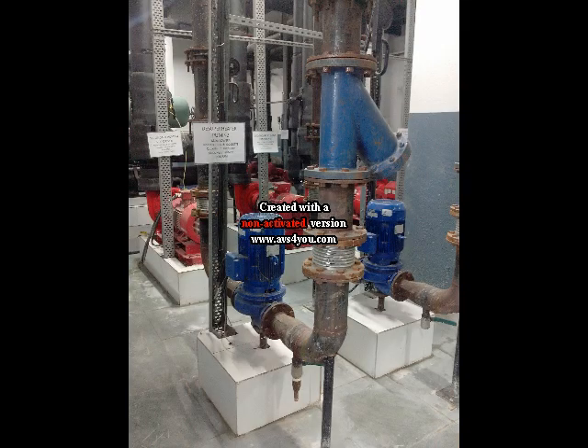These are 2 hot water pumps. These pumps circulate water from the calorifier tank to the desuperheater of the chiller. In the condenser, the circulating water gets heated up by exchanging heat with the high temperature gas of the compressor. From this we can get water up to 50 degrees centigrade. This water can be used in the hot water system.